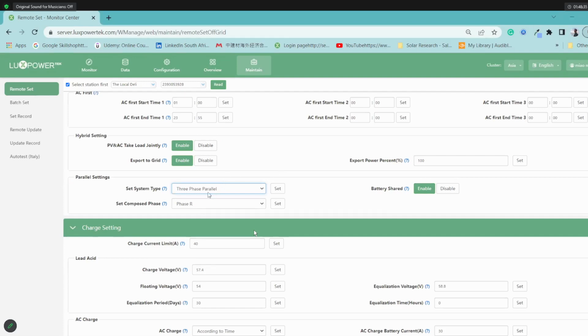Okay, so you will set it to 3-phase, and then what you need to do is cycle through each inverter and program the phase, right? Now, I believe there's a fault that appears telling you the phase was not set correctly. I can't get the wording right.